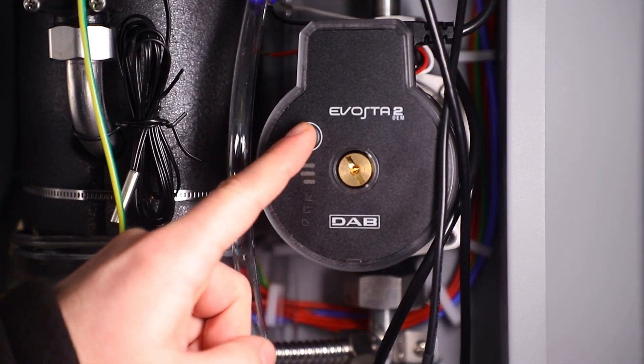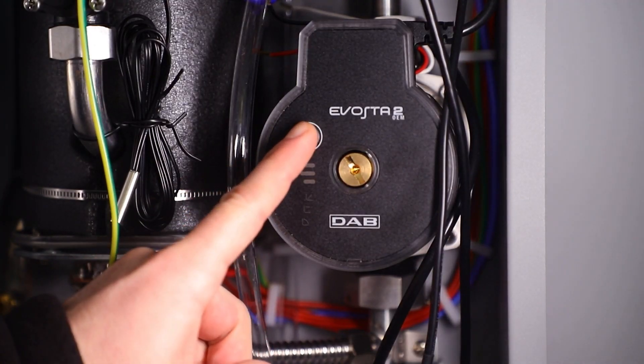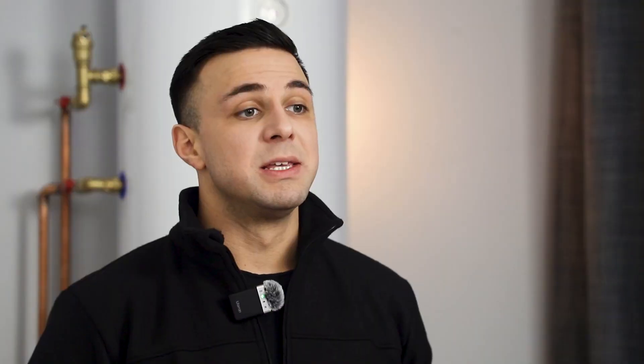Switching between operating modes on the pump is done using the control button. Proportional pressure mode: this mode is highly recommended for use in two pipe systems that include heating radiators. Constant pressure mode: recommended for heating systems with underfloor heating or a single pipe system for heating with radiators. Constant curve mode: recommended for systems with fixed flow rates, for example, an indirect boiler for hot water.